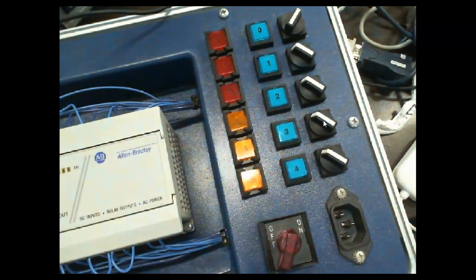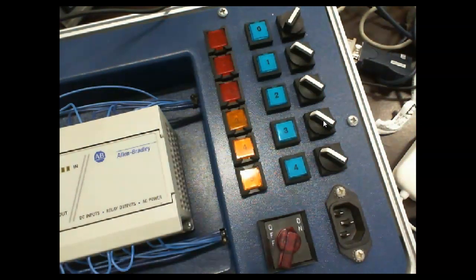The diagram shows me a normally closed, which means I need to use an examine if closed, and you're using an examine if open. So that only comes into play, guys, when you're dealing with inputs. After that, they're normally open, normally closed contacts. If they're inside the logic and they're assigned to an output, it's no big deal. It's only that we've got to consider that if I'm assigning that to an input instruction.